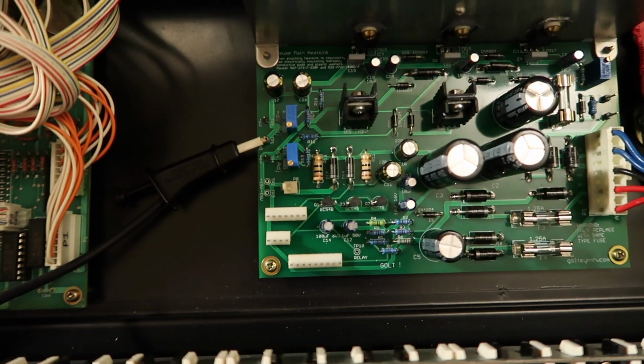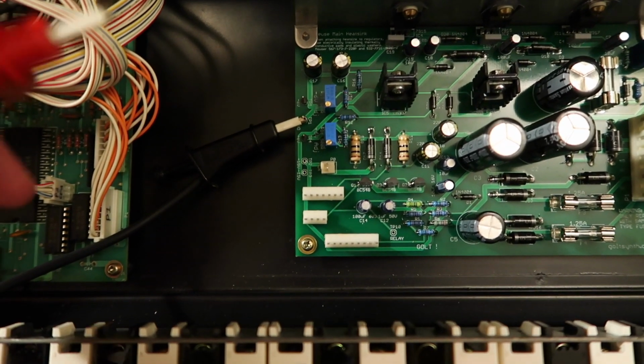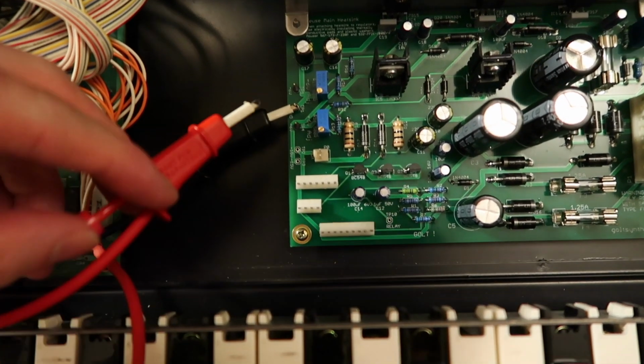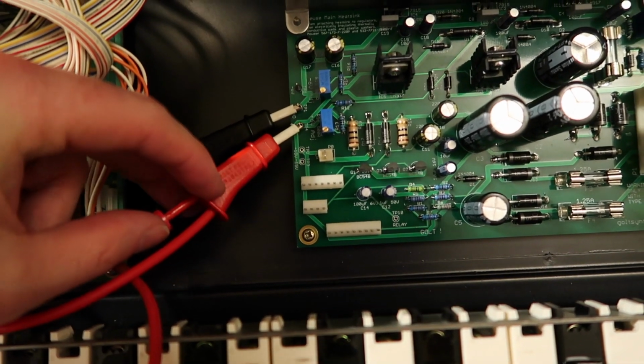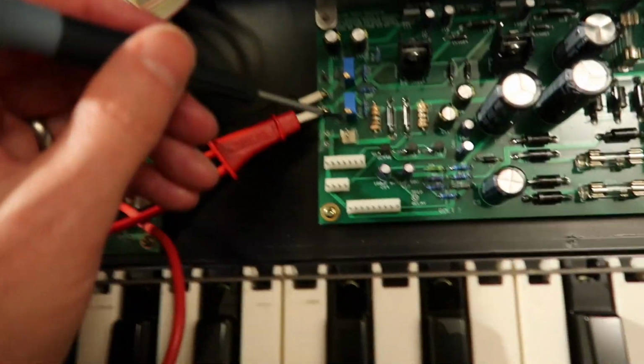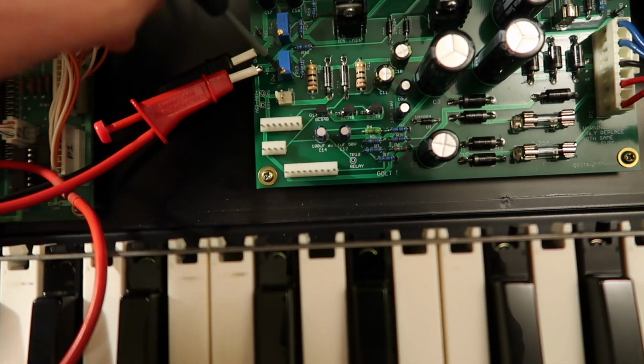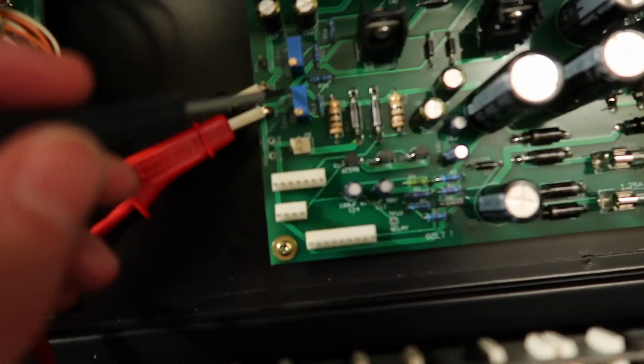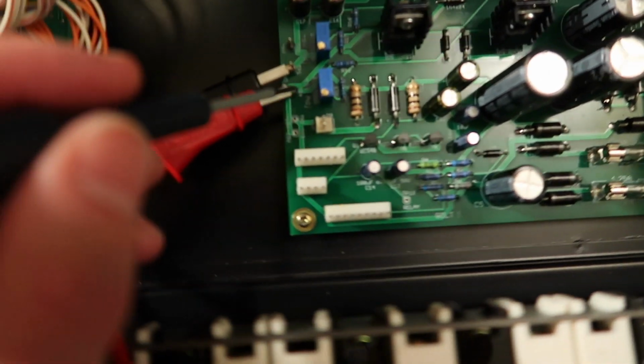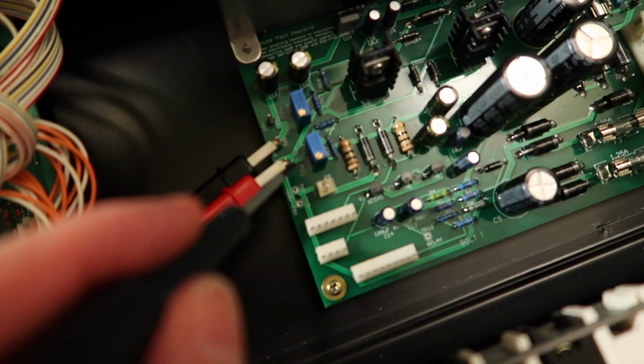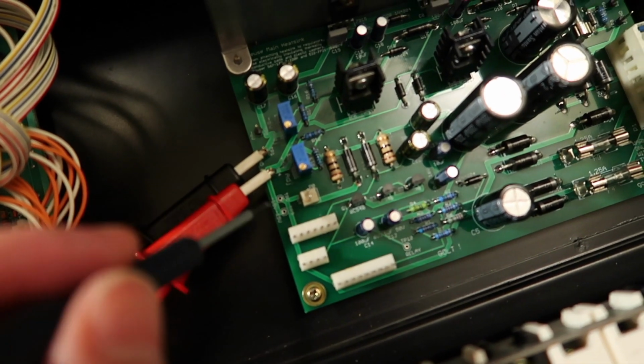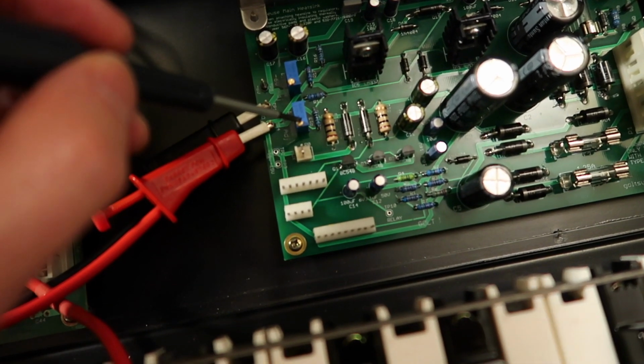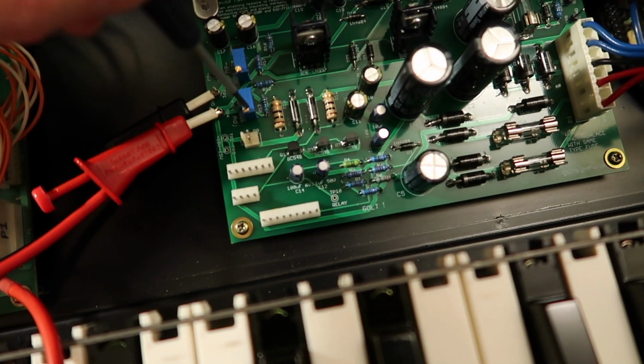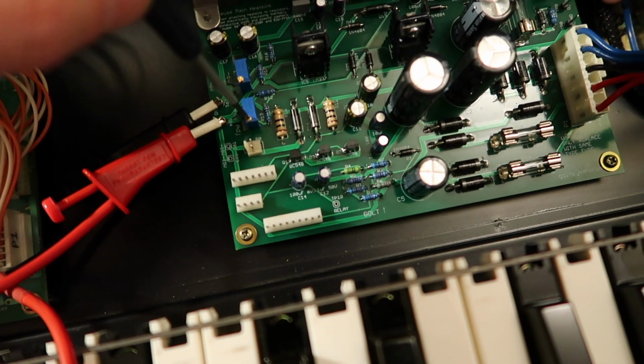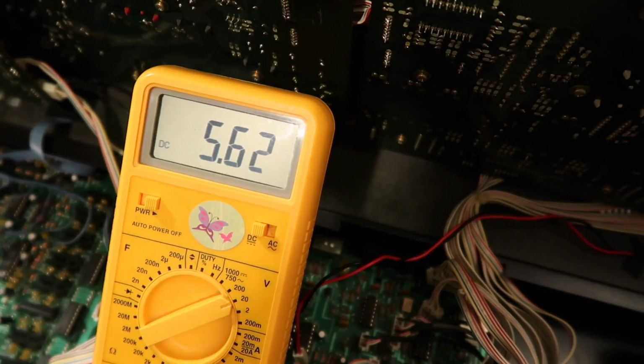So next we just need to calibrate the +6 volts. So that's this test point. I'll just get my screwdriver. And the adjustment point is the one that's labelled on the board. I don't know whether you can see it, there's not enough light here, but it says +6 volt adjust. That's the one directly adjacent to the test point. So if I just put my screwdriver in there, and then we'll have a look at the screen.